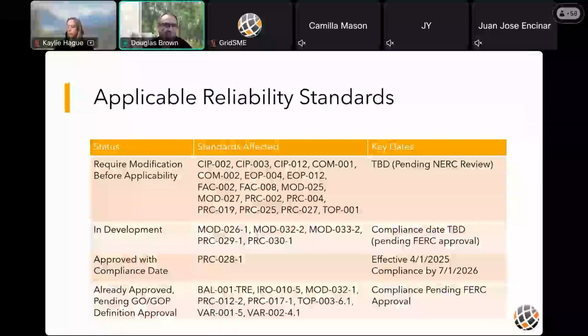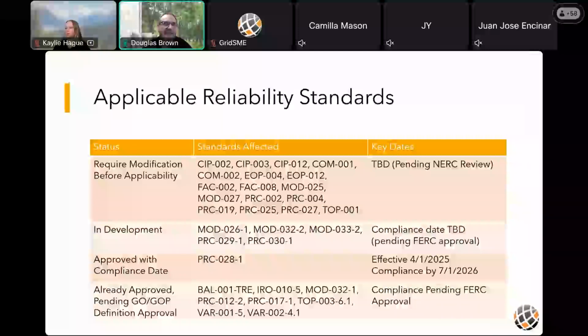I'd expect your plants will have to provide test records and model validation for each of the mod standards covering turbine and generator governor control. You'll need to make sure your models are valid. In a conventional plant, your frequency response was based on how your governor reacted; in an inverter-based plant, you need something that simulates that. You'll also be demonstrating verification of your excitation controls to support volt and var production onto the system.